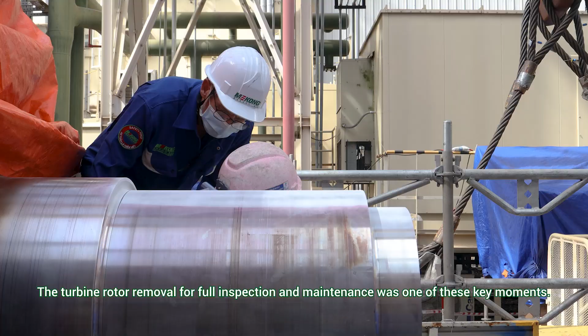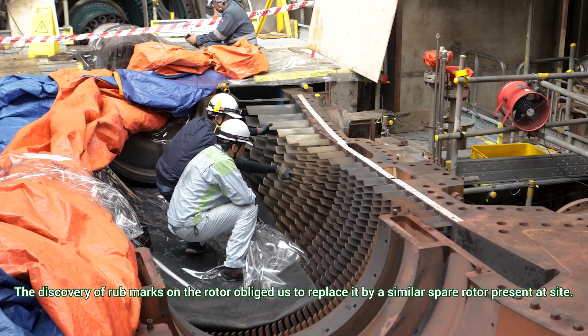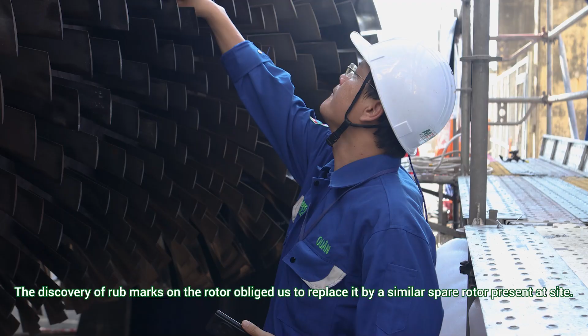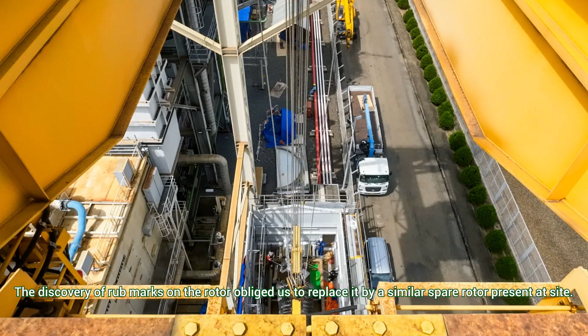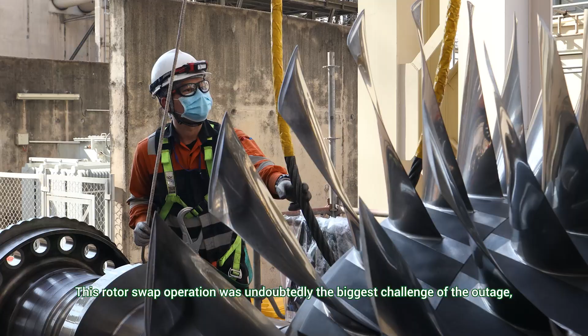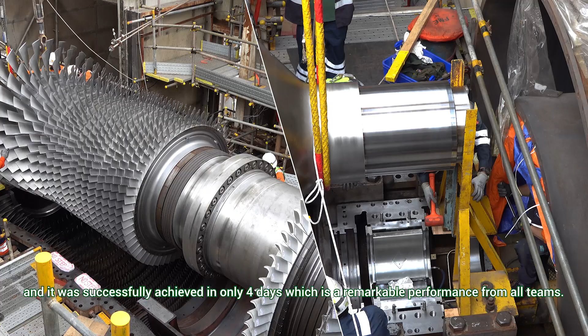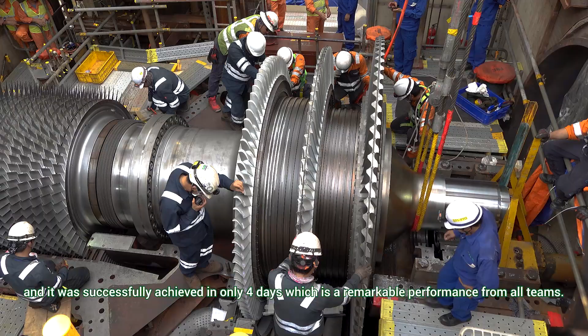The turbine rotor removal for full inspection and maintenance was one of these key moments. The discovery of rubbing on the rotor obliged us to replace it with a similar spare rotor present at site. This rotor swap operation was undoubtedly the biggest challenge of the outage, and it was successfully achieved in only 4 days, which is a remarkable performance from all teams.